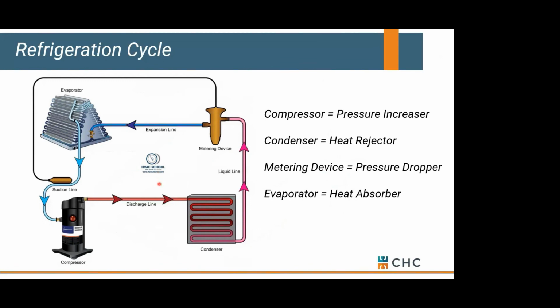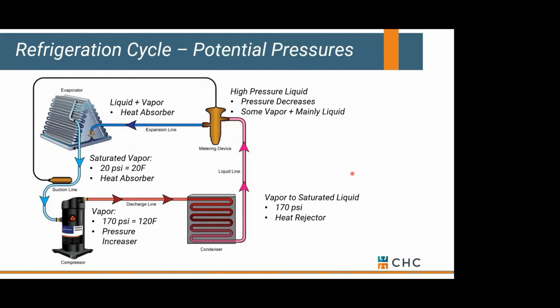I'm a simple-minded person. A compressor is a pressure increaser. That makes sense. Condenser is a rejector. Metering device is a pressure dropper. All real technical terms. And then you could put some numbers to that. And I'm just making up random numbers. But basically, if we're coming off our evaporator at 20 pounds, our compressor might increase that up to 170 to give us the ability to generate 120-degree domestic water. Now, in reality, heat pump water heaters can generate up to 160-degree domestic water. Okay, so they're running much higher pressures, but just maybe a quick look at some sample pressures and temperatures.